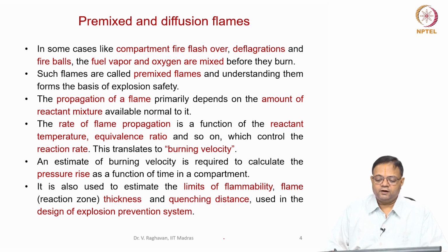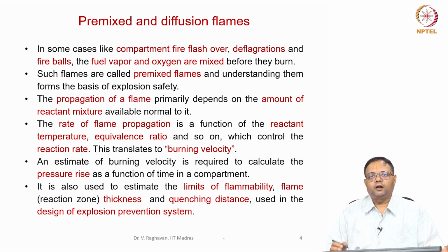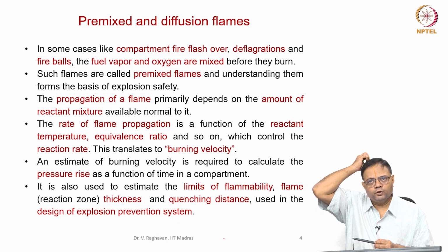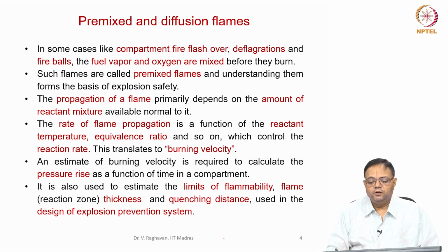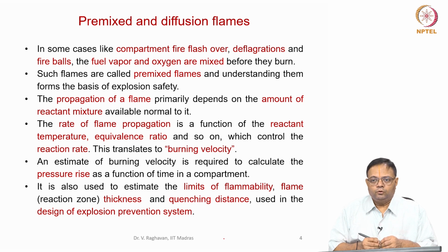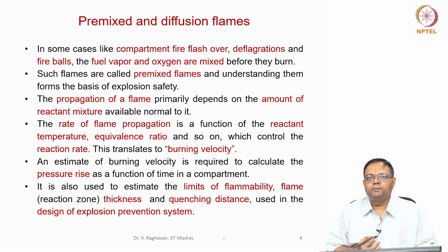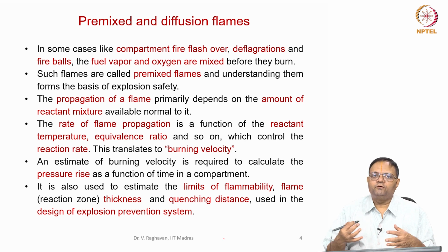Now, let us consider a case of fire occurring within a compartment or an enclosure. What happens here is, there is a room which has some doors or windows, some limited ventilation is present. So, in this phenomenon, due to the available oxygen, some commodities burn, but then due to limited ventilation, the commodities may not be completely burning, or the fuel vapors which are hot enough will be generated.